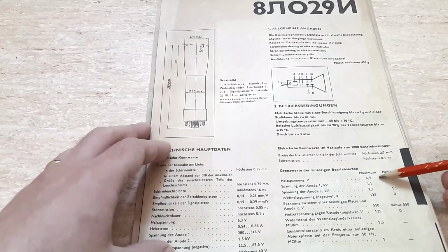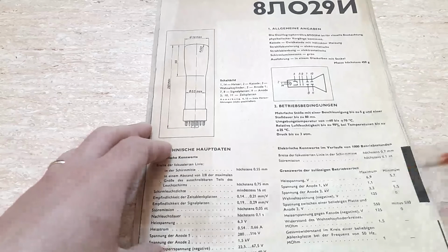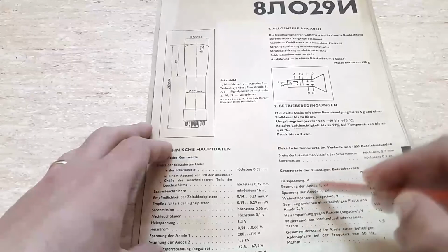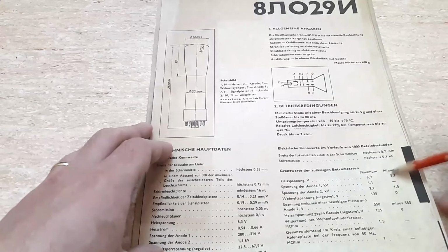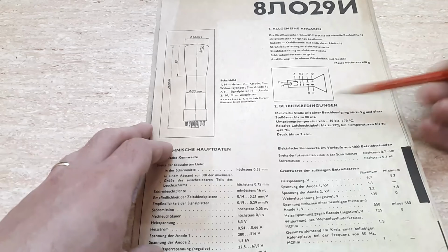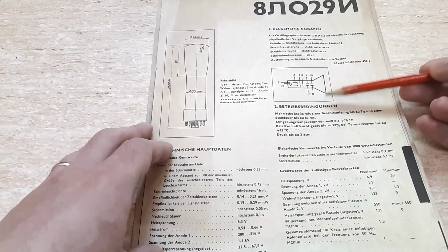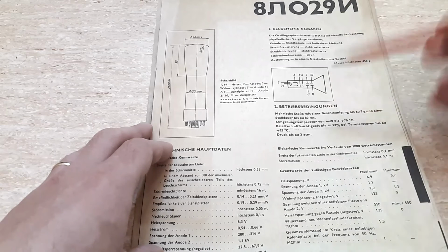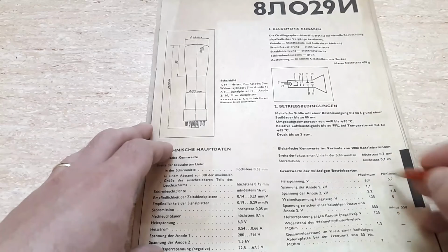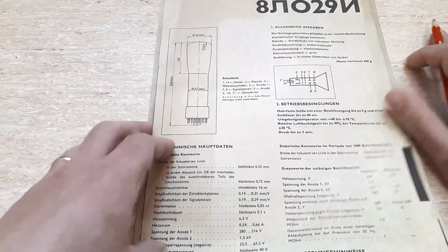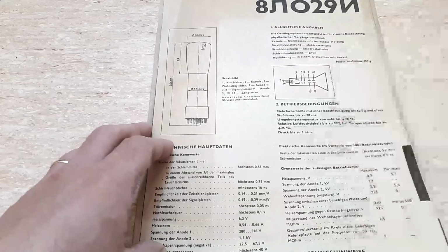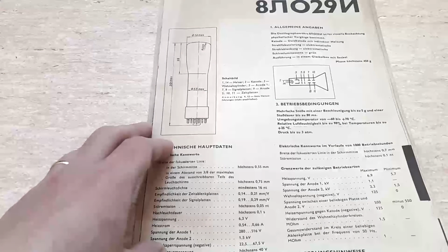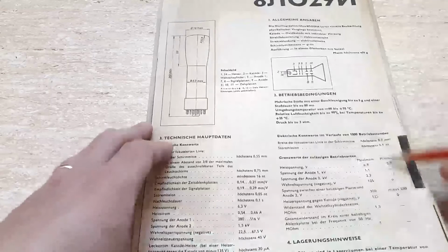And what we are seeing over here, 6.9 volts. This is the maximum voltage for the filament. 6.9 volts maximum, 5.7 volts minimum. I assume that this is in order to make a reliable picture with the same characteristics. In general, if you would underdrive the filament, you would have better longevity, but however, you would have to trade off some of the contrast and brightness capability on the screen.